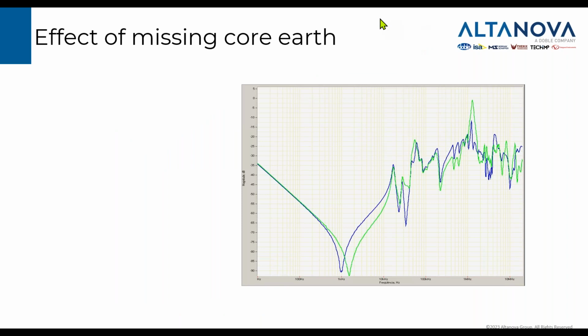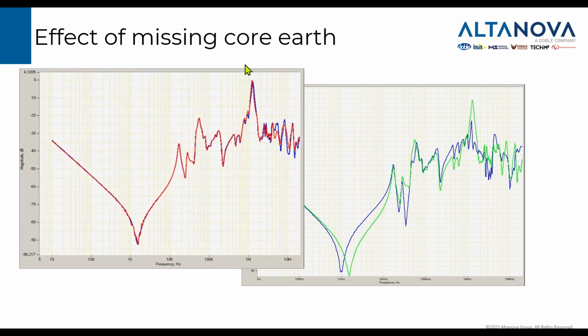Another mistake that can be made, or influencing factor that needs to be considered, is core earth. It can happen that the transformer is tested, that core and frame earthing is disconnected for the purpose of insulation resistance measurement, and it can either be forgotten to be put back in place, or maybe be made by another person from the team while another one is preparing for an SFRA test, and then the test is performed and traces do not match. So this is such an example where two traces were measured on the transformer with and without the earth connection of the core and frame. When the transformer was tested again with that reinstated, then the new trace was as expected.